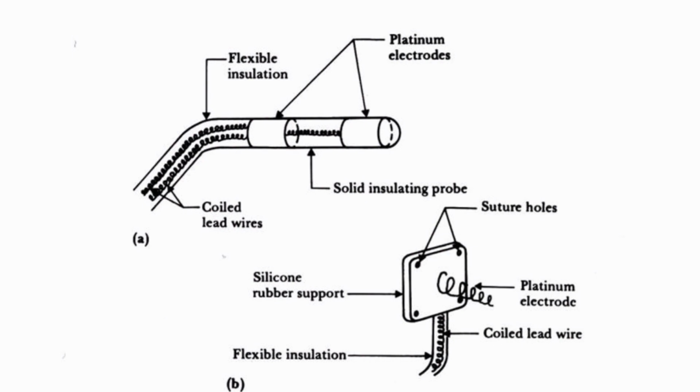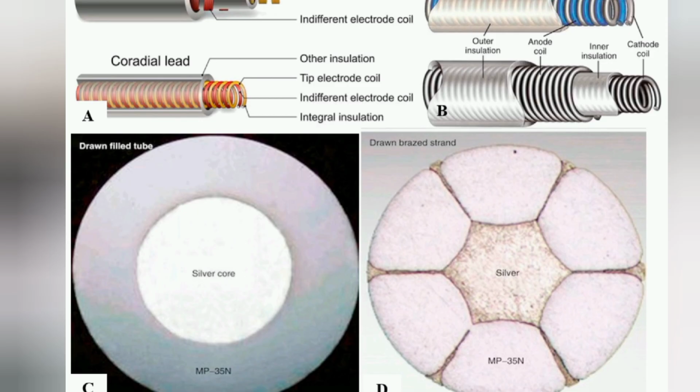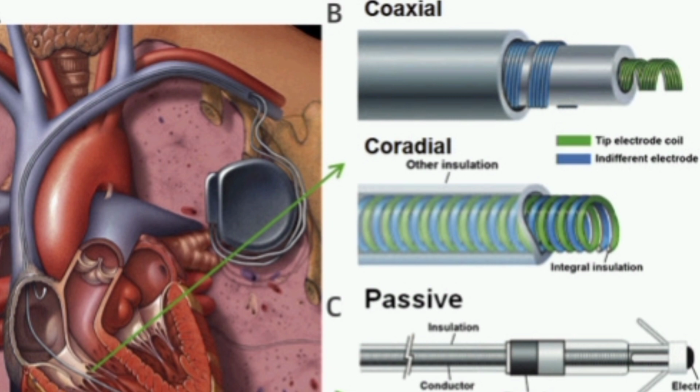The circuit is usually made up of modified silicon semiconductor. For pacing leads, the materials generally used are a composite wire conductor strand consisting of a thick, strong body of MP-35N or titanium which has been filled with a center core of low resistant metal silver and encased in a shell of platinum alloy.